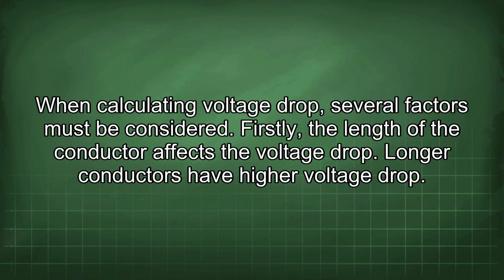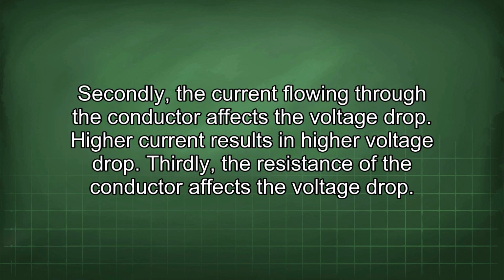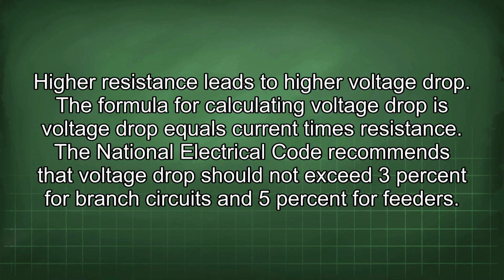When calculating voltage drop, several factors must be considered. Firstly, the length of the conductor affects the voltage drop. Longer conductors have higher voltage drop. Secondly, the current flowing through the conductor affects the voltage drop. Higher current results in higher voltage drop. Thirdly, the resistance of the conductor affects the voltage drop. Higher resistance leads to higher voltage drop. The formula for calculating voltage drop is voltage drop equals current times resistance. The National Electrical Code recommends that voltage drop should not exceed 3% for branch circuits and 5% for feeders.